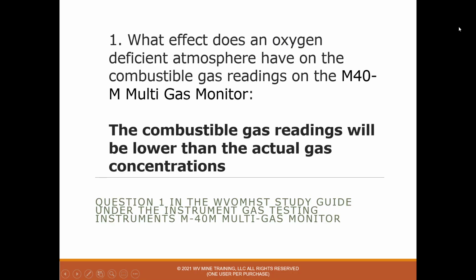Question 1, what effect does an oxygen-deficient atmosphere have on the combustible gas readings of the M40-M multi-gas monitor? And the answer to that is the combustible gas readings will be lower than the actual gas concentrations. So if oxygen is lower than normal, where normal oxygen is like 20.8, how is that going to affect your combustible gas readings? And they will be lower. So if oxygen goes down, your combustible gas readings will go down as well from what they actually are.